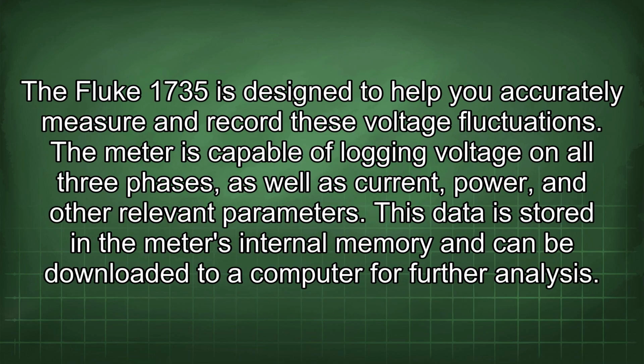The Fluke 1735 is designed to help you accurately measure and record these voltage fluctuations. The meter is capable of logging voltage on all three phases, as well as current, power, and other relevant parameters. This data is stored in the meter's internal memory and can be downloaded to a computer for further analysis.